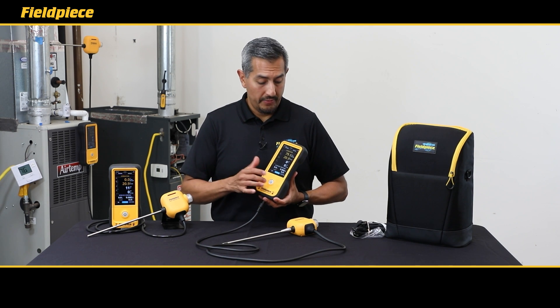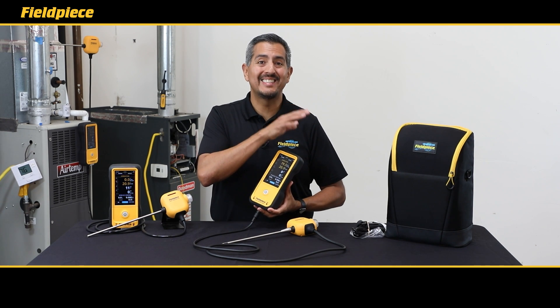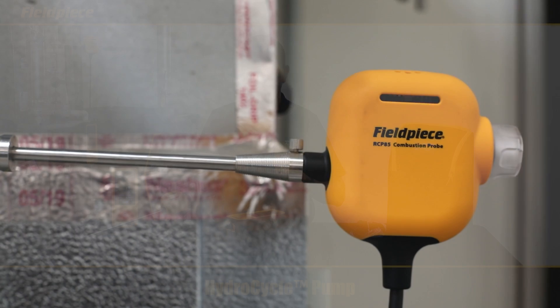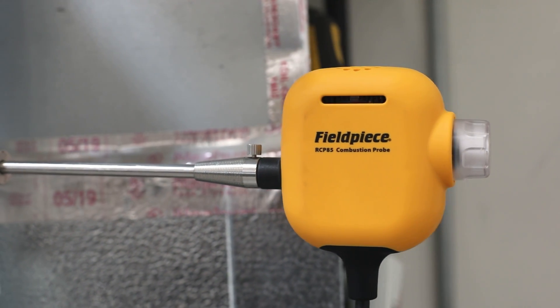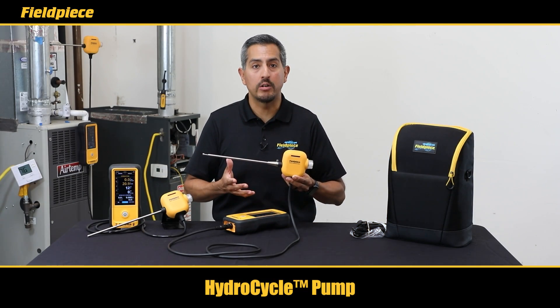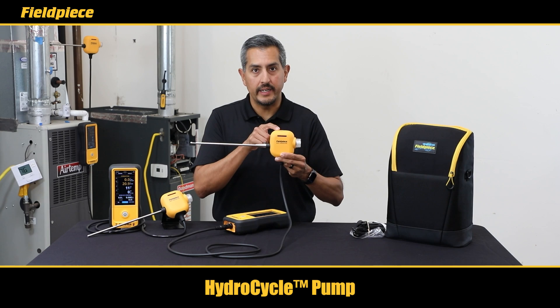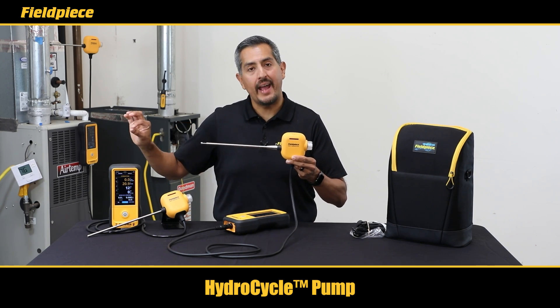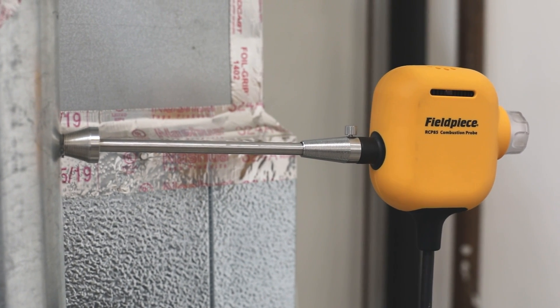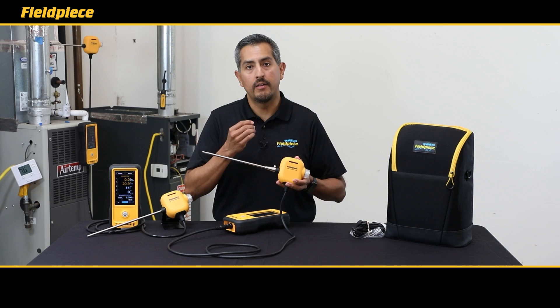You may have noticed the Cat85 doesn't have a water trap — and that brings us back to the HC, which stands for HydroCycle. The HydroCycle pump that comes with your Cat85 is another patent-pending innovation from Fieldpiece that eliminates the need for a water trap. The HydroCycle pump brings in the water vapor from the flue, cools it, condenses it, and spits it back out into the flue, thus eliminating the need to empty or have a water trap at all. It's another innovation to help you do your job easier, faster, and better.